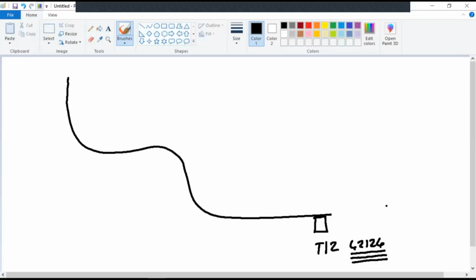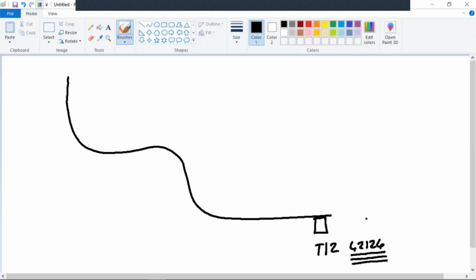they can tell you exactly where you're at on a map. They can tell you the address. They'll tell you which phase you're working on. They'll tell you if you're working on three phase. They'll tell you the feed direction. They have a lot of information in their mapping system that they're able to share with you. Now, do understand, they're sharing information from a software system. You have to verify it.